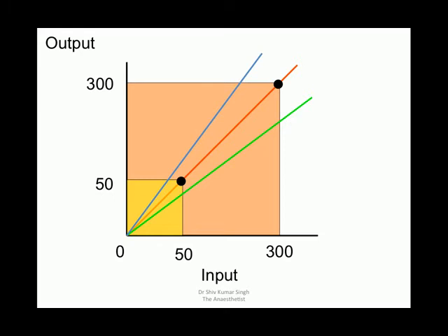If the patient's blood pressure is exactly 180, it will likely show you a blood pressure of say 90 or 100. Whereas in the blue one, when your blood pressure is 90, it will show 120. So these machines, or the transducers, need to be recalibrated.